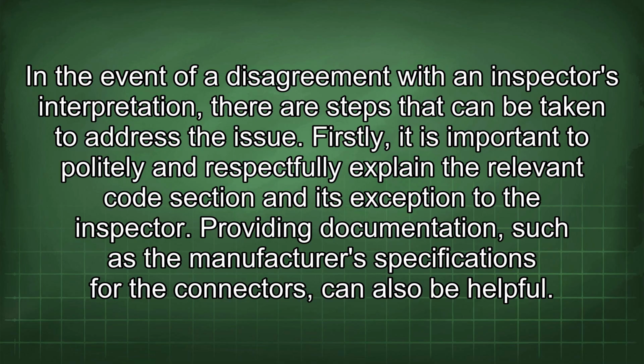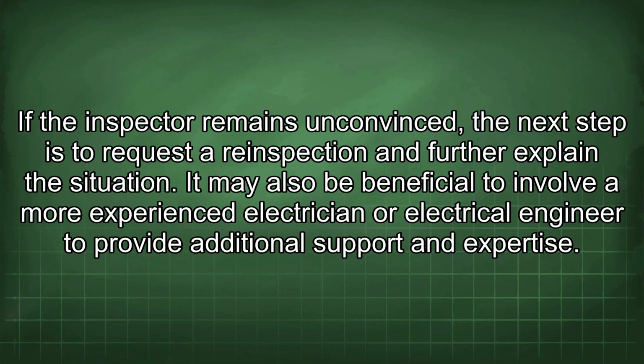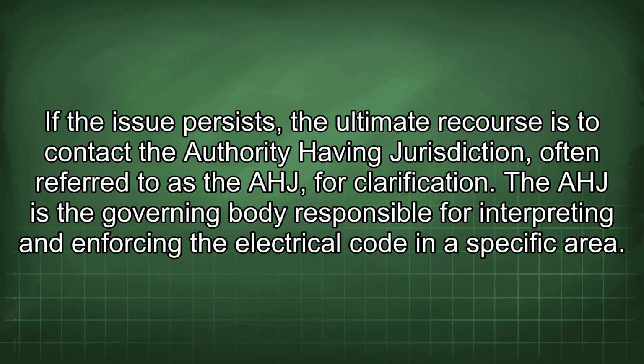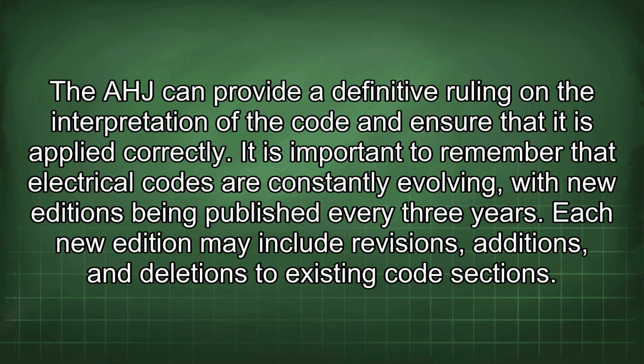In the event of a disagreement with an inspector's interpretation, there are steps that can be taken to address the issue. Firstly, it is important to politely and respectfully explain the relevant code section and its exception to the inspector. Providing documentation, such as the manufacturer specifications for the connectors, can also be helpful. If the inspector remains unconvinced, the next step is to request a re-inspection and further explain the situation. It may also be beneficial to involve a more experienced electrician or electrical engineer to provide additional support and expertise. If the issue persists, the ultimate recourse is to contact the authority having jurisdiction, often referred to as the AHJ, for clarification. The AHJ is the governing body responsible for interpreting and enforcing the electrical code in a specific area. The AHJ can provide a definitive ruling on the interpretation of the code and ensure that it is applied correctly.